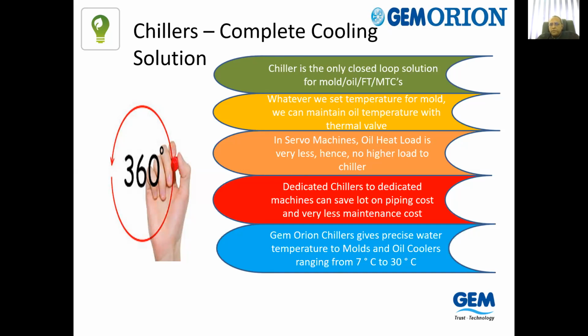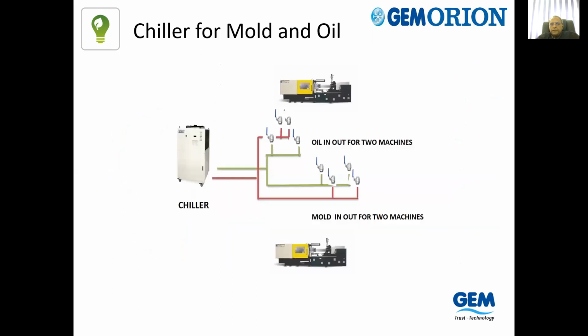For example, if your wet bulb is 27 and you want to run the cooling water during that wet bulb at 28, you can run the unit also. The capability is very wide. The set points can be from about 7 degree up to 30 degree, and for the inverter chiller, now we are trying to extend it from plus 5 to 35 degree.